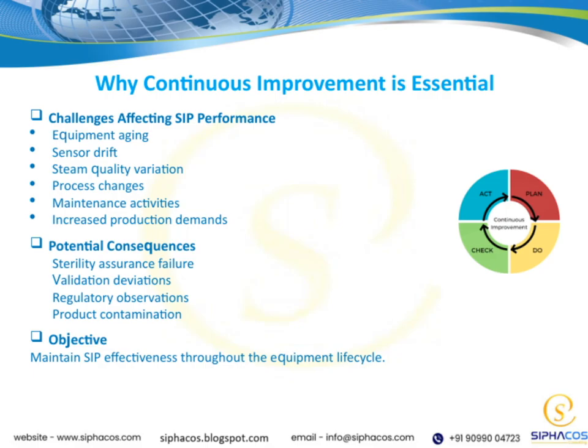Over time, equipment ages, sensors drift, steam quality varies, and processes change. Maintenance and higher production demands add more complexity. If we don't keep up, the risks grow: sterility assurance can fail, validations can slip, regulators may raise concerns, and worst of all, contamination can happen. Our goal is clear. We need to maintain sterilization effectiveness throughout the entire equipment lifecycle, no exceptions.